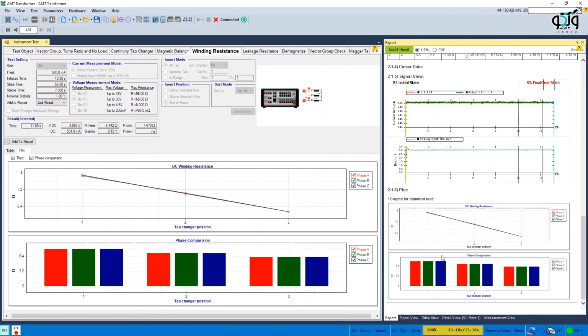Some points about the winding resistance test. Since these transformers have a huge self-inductance, injecting DC current causes huge voltage spikes, and the more the injected current, the bigger the created voltage. This voltage causes two problems. The first problem is an overvoltage error on the inputs of the device. As you know, if the voltage of the input is bigger than the value specified for it for more than 0.5 seconds, the device displays an error. Therefore, if the caused voltage spikes have too long durations, the device may display an error.